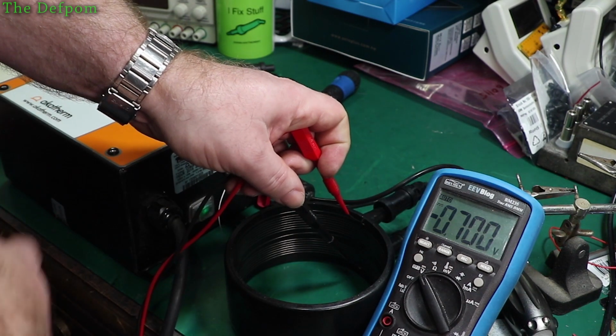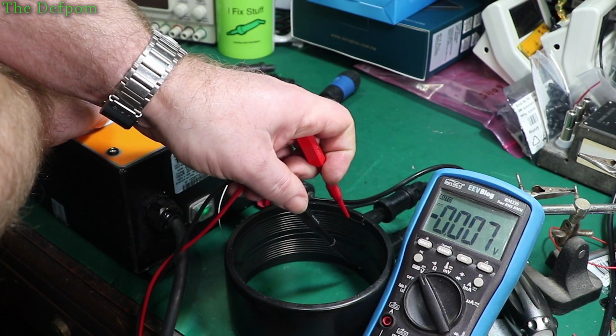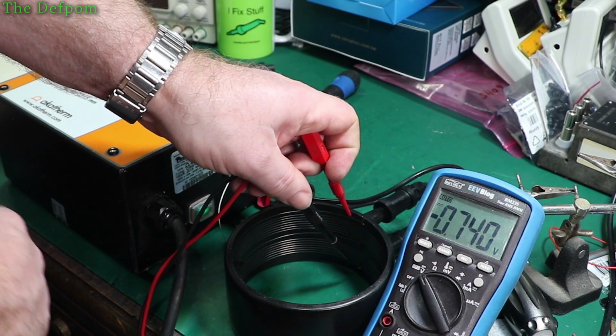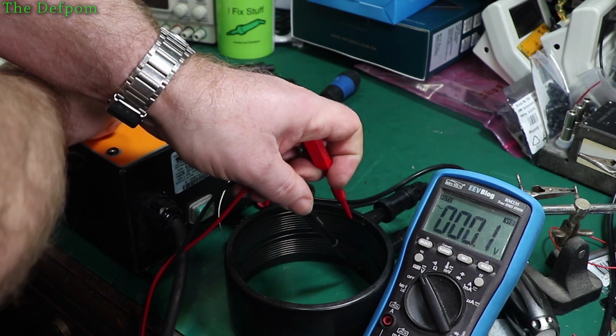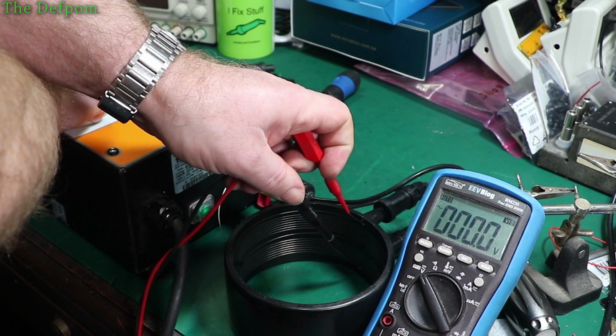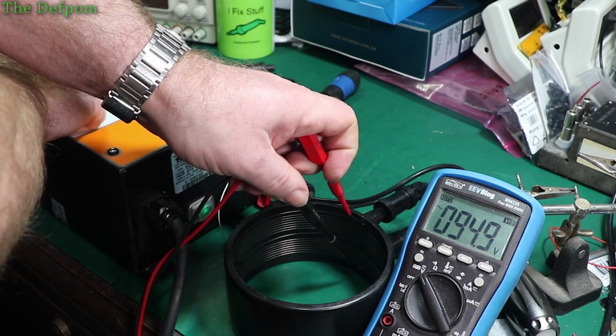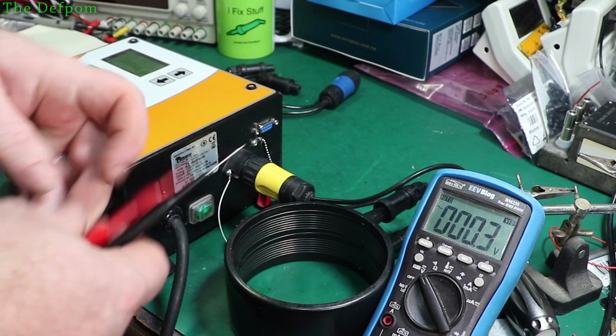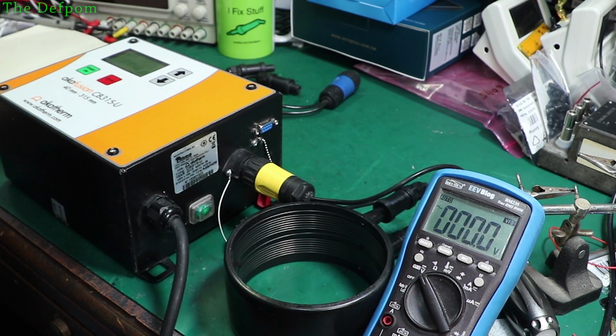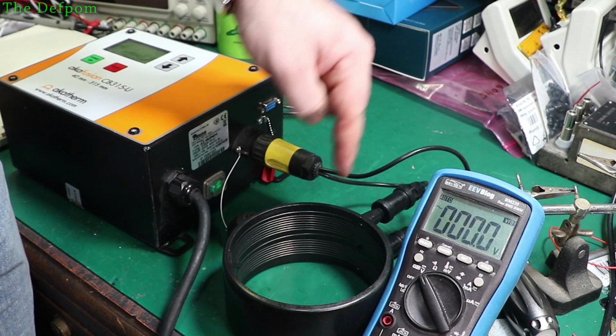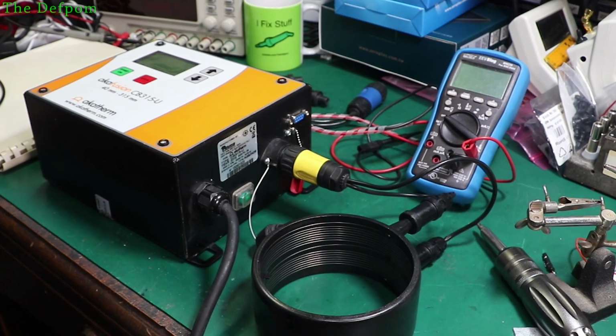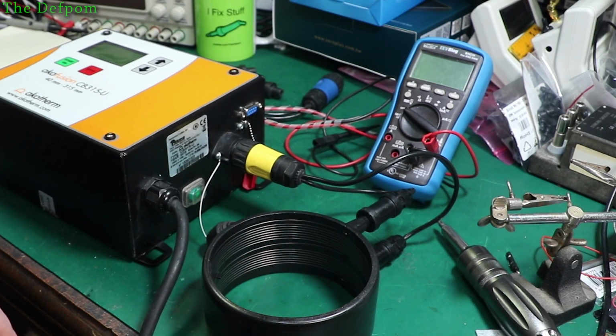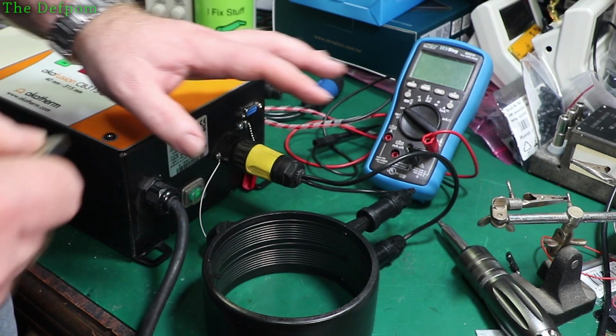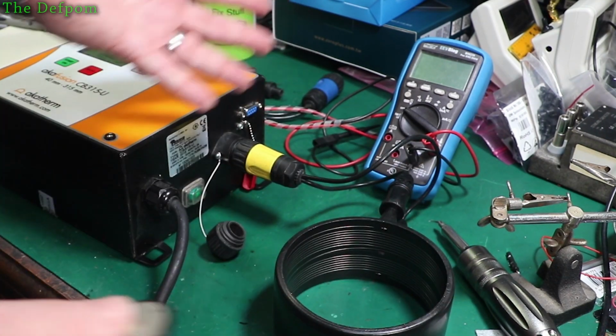Alright, so I'm on DC first, see if we get any DC voltage. Nope. It's obviously AC. Okay, let's try AC. See what we get. Okay. So that's 95 volts AC on a loaded coil, 20 ohm coil. So now we know what the voltage is, we know what the resistance is, so we can calculate the power. Okay, so according to the calculators, the resistance of this coil with that voltage across it, it's 4.75 amps and 451 watts is the consumption into this coil here. I've got a baseline, that's great.